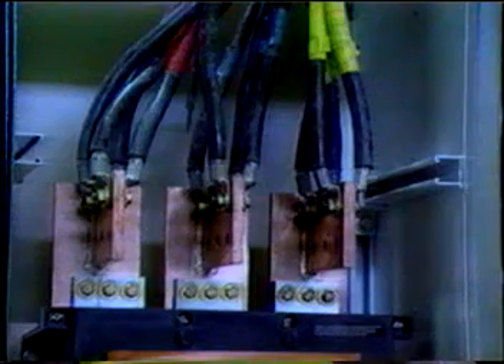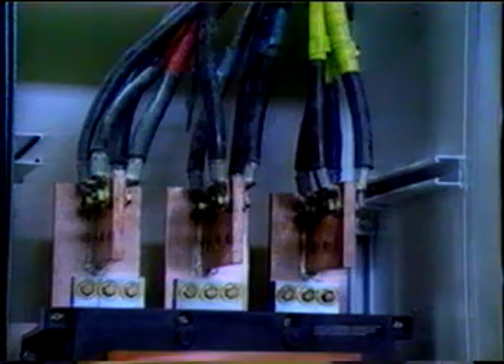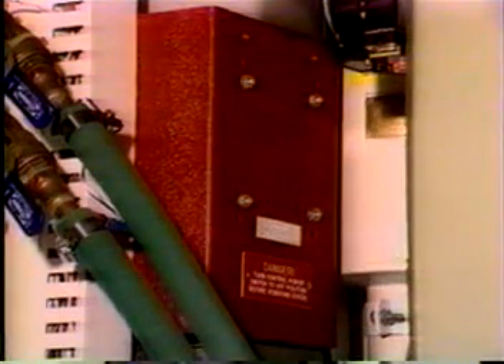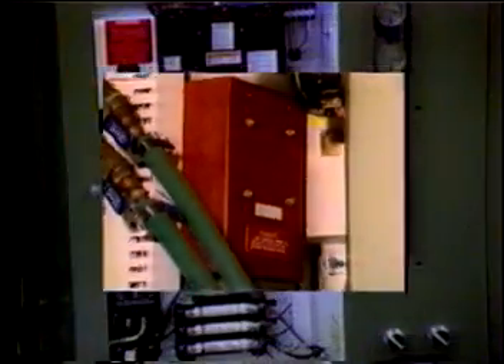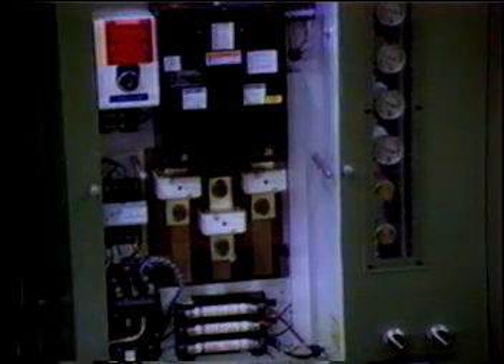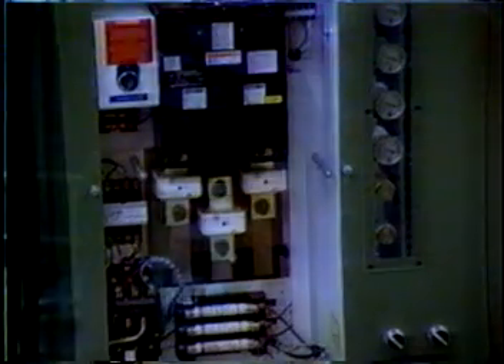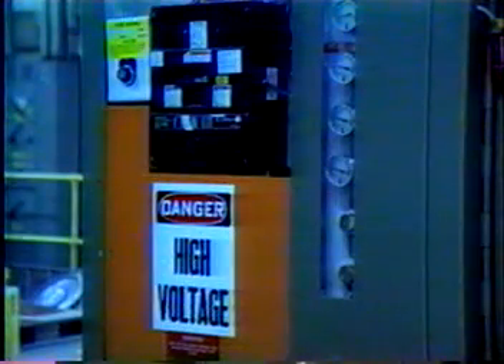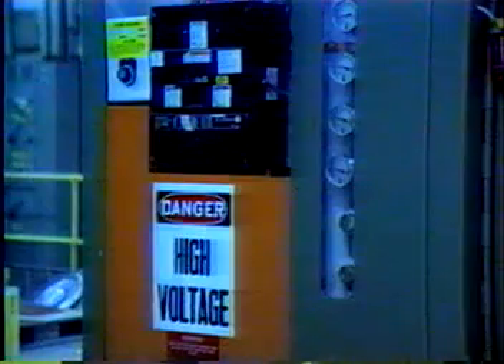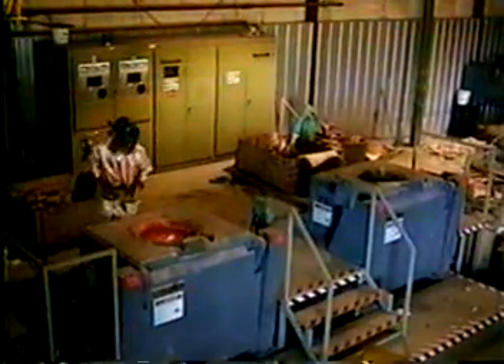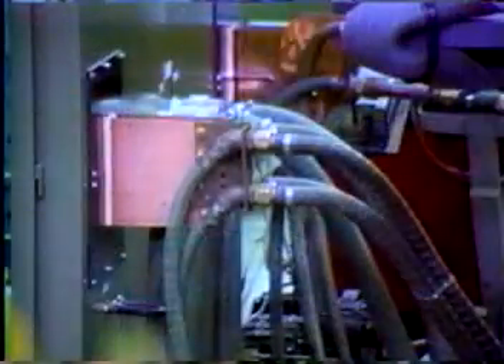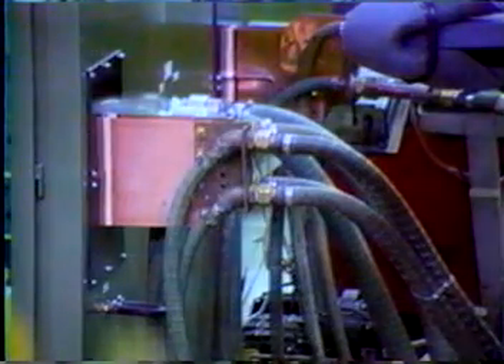Be aware that there are some areas inside the power supply that are on the incoming side of the breaker and remain energized even after the breaker is off. In newer units, these are marked and protected by individual covers. If you remove such a cover, you must replace it after the area has been serviced. This will help protect the next person servicing the unit from accidental contact with the energized component. If the power supply energizes more than one furnace, leads to the furnace undergoing maintenance or repair must be disconnected from both ends of the coil and the furnace induction coil grounded.